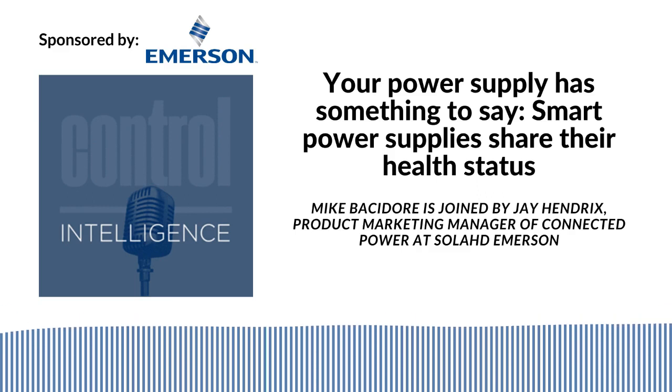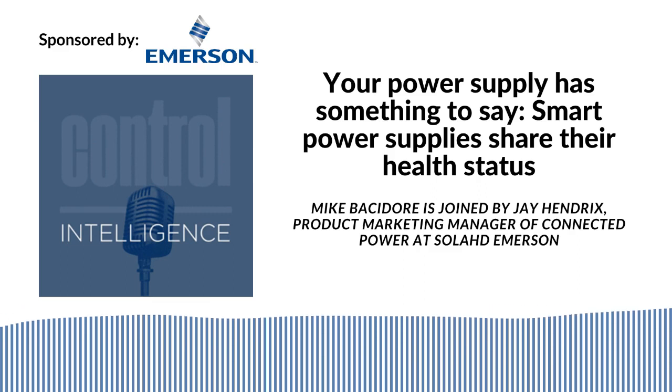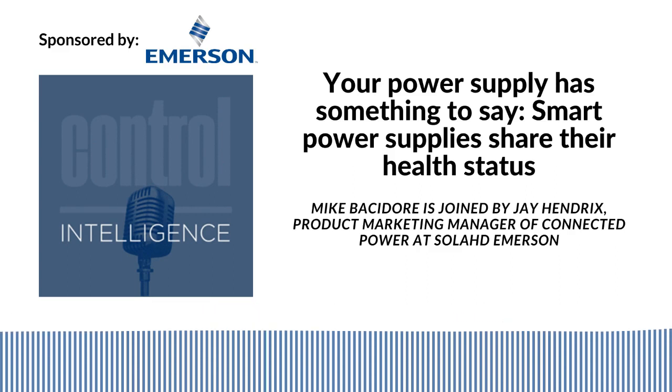Absolutely. So what about a power supply that has a DCOK contact? Isn't that good enough? Well, that has its use, and that's been used for many years, and it's still used today, and it's still going to be used going forward. That DCOK contact provides you an indication that the DC power output is still good. And that relay would open up if there's no DC power. That's very useful in redundant applications or in a safety shutdown sequence, for example. But once that opens up and the DC power is lost, it's too late at that point to do anything about it. You've already lost the DC power. So it's really an after-the-fact indication.